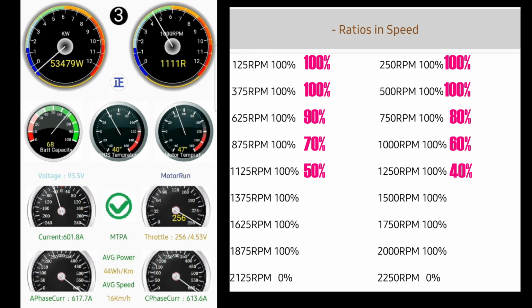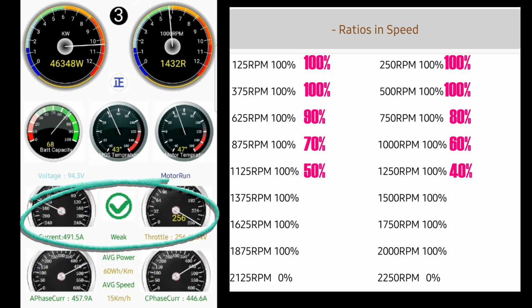The next event we want to look for is where field weakening starts. And this test is done, remember, with everything in ratio and speeds at 100%. Keep coming up right there. 1432, weak. Now we have back EMF exceeding or equal to EMF. And when that happens, the controller is going to enter field weakening and limit phase amps. And you see they drop down to 457. They limit it by lowering line amps. You can see line amps are down to 491.